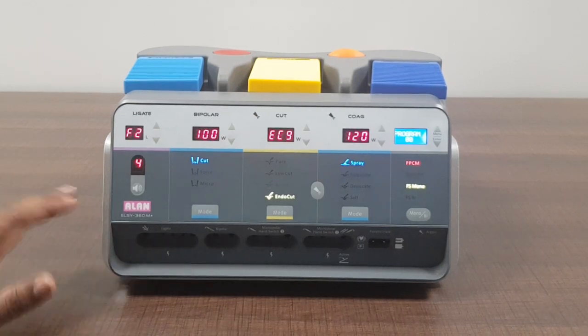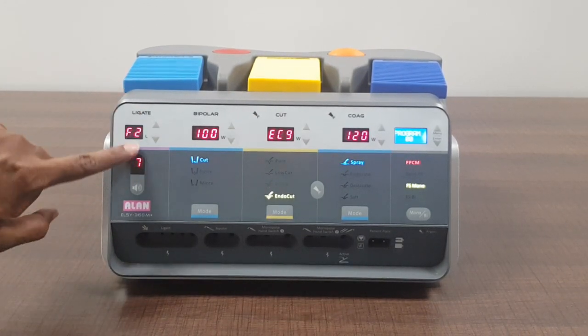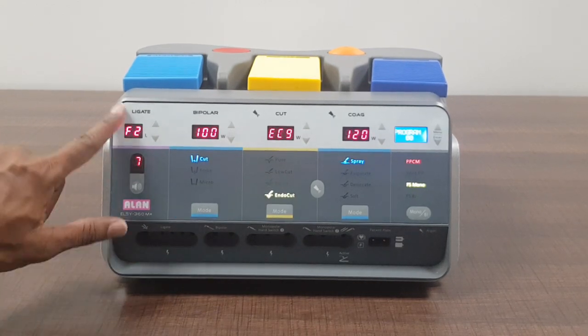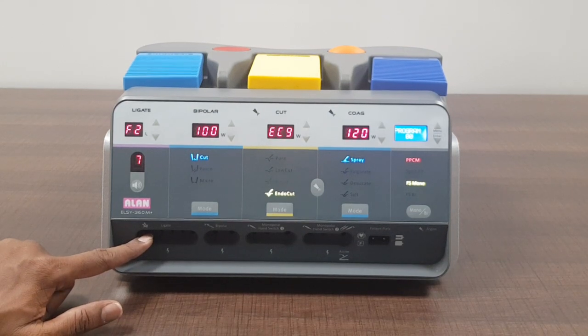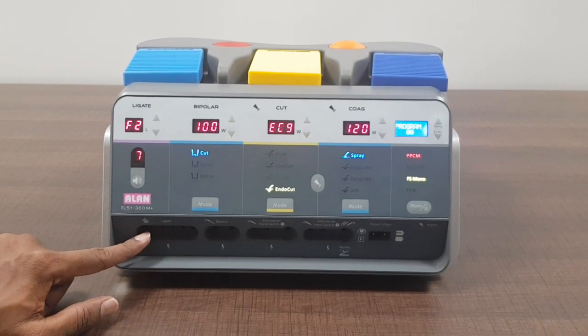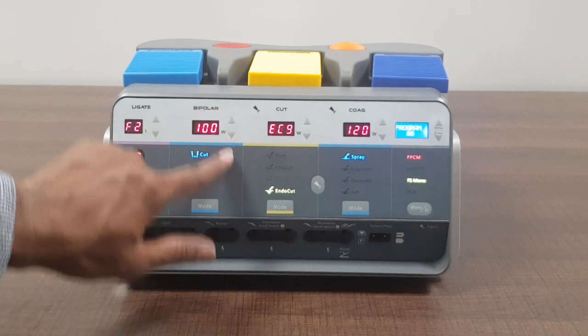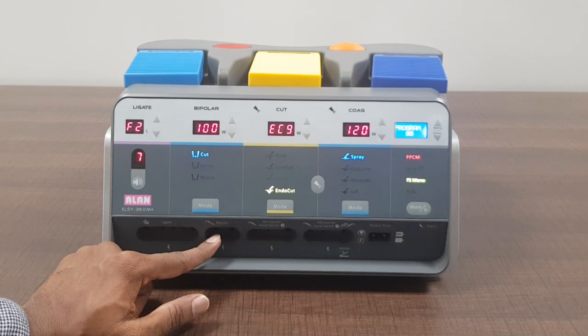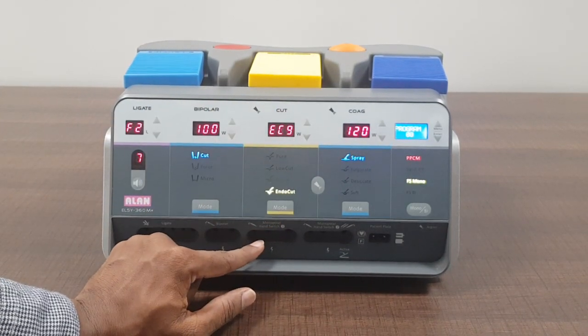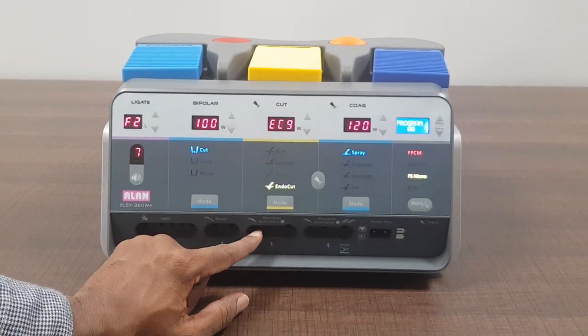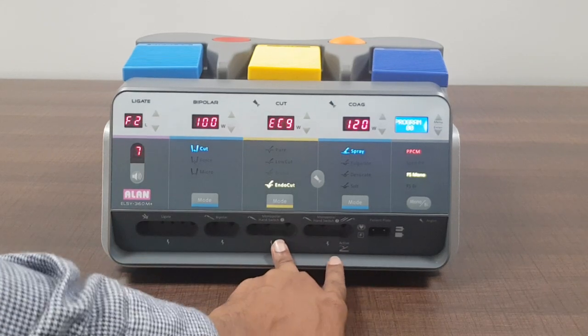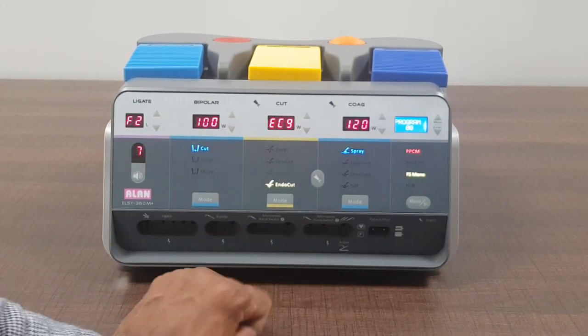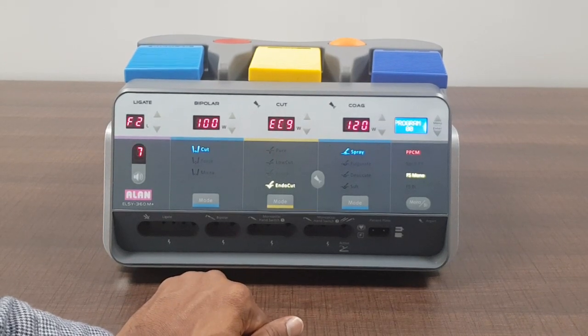And just to give you the other glimpse, this is for volume increase and decrease. And whatever modes you keep here you have to connect the ligature, this is the corresponding port for ligate. You have to connect the open vessel sealer or the laparoscopic vessel sealer or the golden tip. And this is bipolar, whatever modes you keep here the corresponding output comes from here. This is for a monopolar cut so corresponding output comes from this monopolar here. And for coagulation also it will come from here but we have two monopolar outputs for monopolar cut and coag simultaneously you can use for coagulation in certain surgeries. And this port is for a patient plate.